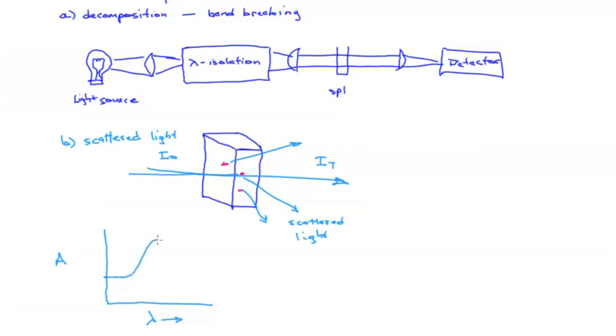Since particles tend to scatter light over a wide range of wavelengths, it is common to see an absorbance band sitting on top of the scattered background. A common remedy to a scattering problem is to measure the peak of interest above the absorbance of the background. As illustrated here, a straight line is drawn in to approximate what the background is below the peak of interest. And the difference between that line and the absorbance at the height of the peak is taken as the estimate of the absorbance that's proportional to the concentration of our analyte.